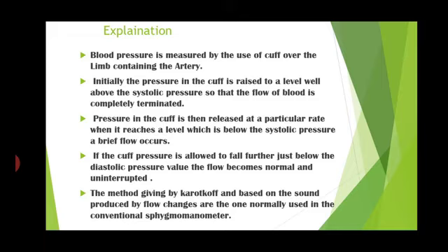When it reaches a level below the systolic pressure, a brief flow of blood occurs. If the cuff pressure is allowed to fall further, just below the diastolic pressure value, the flow becomes normal and uninterrupted. At that time, the sound from the cuff disappears, or it may change. The method using the cuff and based on the sound produced by flow changes is the one normally used in the conventional sphygmomanometer.